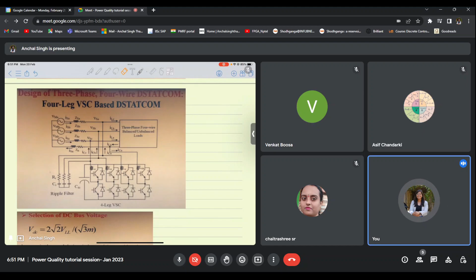And then there is the design of three-phase four-wire STATCOM. The equations for three-phase four-wire are almost similar. The only difference in three-phase four-wire is the derivation of the capacitor. What happens in three-phase four-wire is it could be almost similar to the design of a single-phase converter. In a single-phase converter, when unbalance occurs, due to the presence of unbalance, a second harmonic component appears in the DC link voltage. So you could do a theoretical derivation, or you could do a simulation in order to understand the second harmonic component.